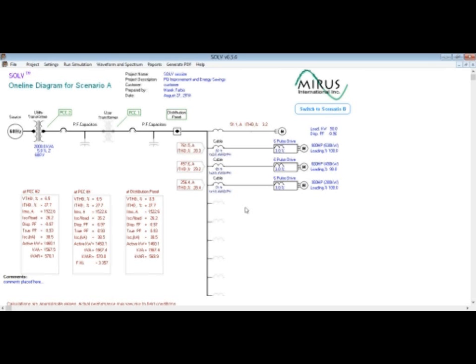At PCC2, your report gives a TDD value, but in reality, if this was a utility transformer, it would supply many more loads than those only connected to the user transformer. Yes, this is true. However, the TDD value measured at the utility transformer would include all other loads, and there probably would be some other cancellations and reactions with other users. So we only show what effect these particular loads that we try to simulate for the one customer would have on the utility transformer, regardless of other users.